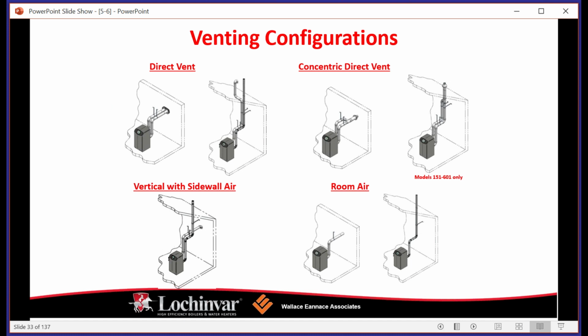We can do vertical venting with sidewall air. We can do room air. So again, we don't necessarily need to have our flue gases expelled and our combustion air coming through the same plane. If it's easier for you to take your fresh air intake from the side of the building and vent out the top, that's perfectly acceptable. And on the lower right-hand side of the slide, you see room air.